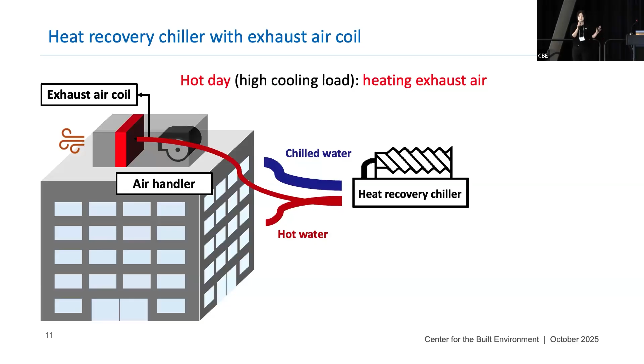These coils reject or recover excess heat through the exhaust air stream. So it is especially effective for buildings with high ventilation requirements. On a cold day, heating demand is high while cooling demand is low. Heat recovery chillers run to meet the high heating demand, and excess chilled water is supplied to the exhaust air coil to cool down the exhaust air. On a hot day, the situation is reversed. So we have higher cooling demand, and the excess hot water is supplied to the exhaust air coil to heat the exhaust air.